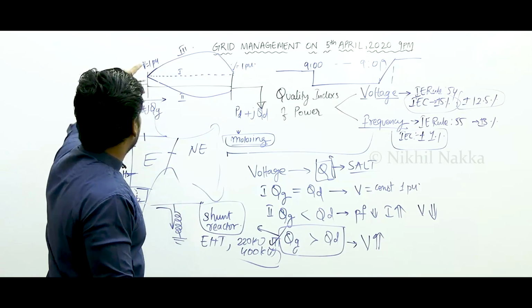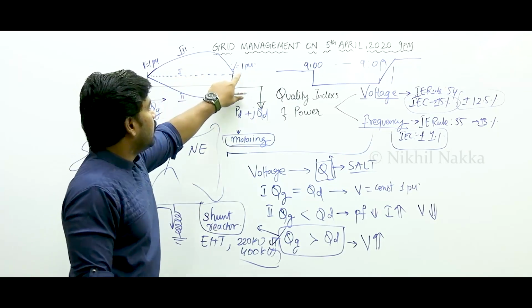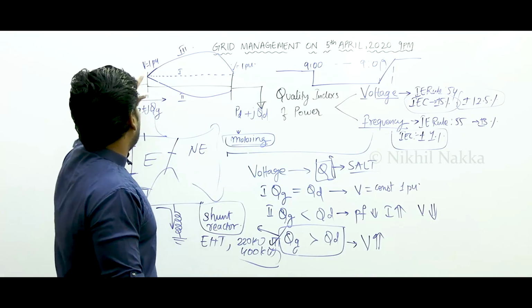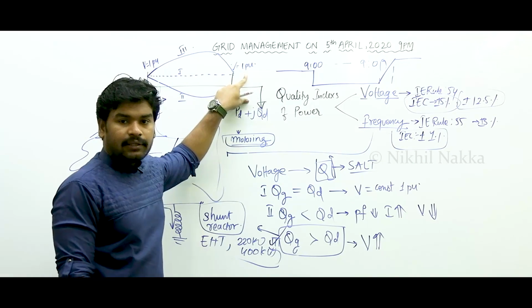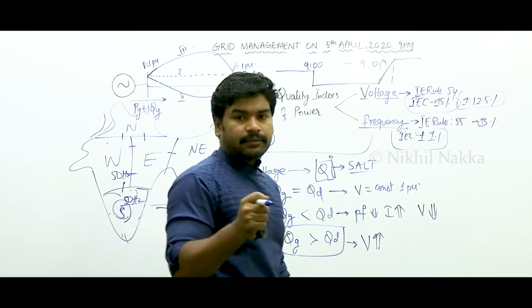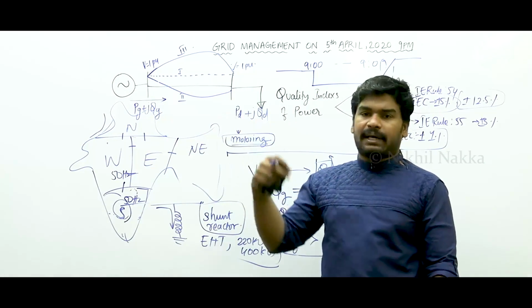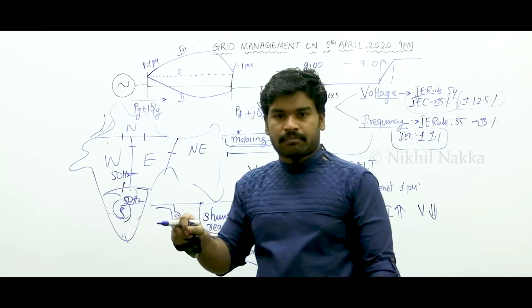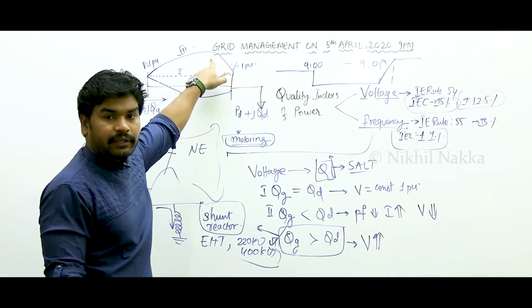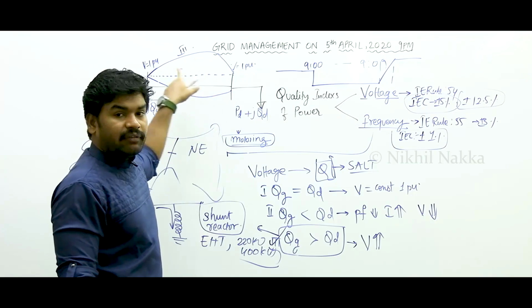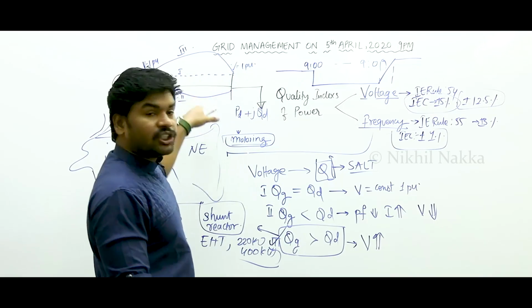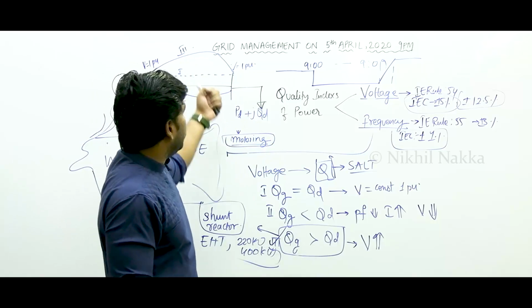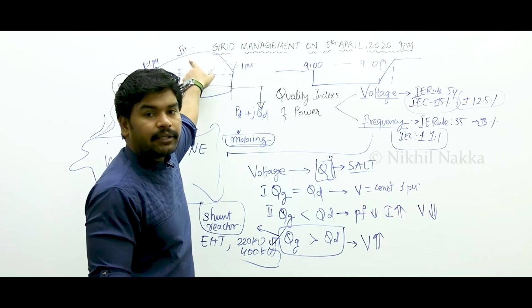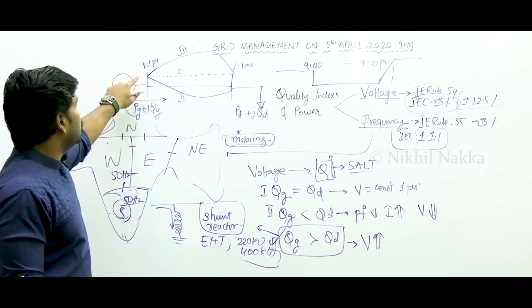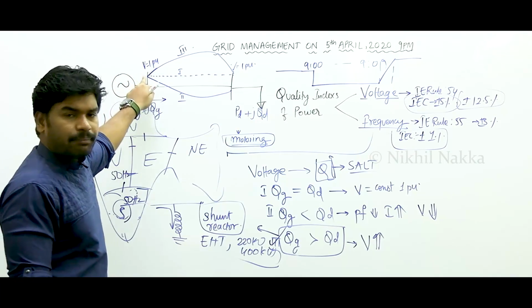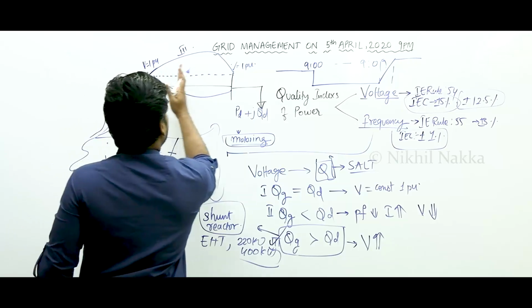What happens is, here you have transformers, and here too you have transformers. At the generating side and at the consumption side, maintaining voltage is a very strict parameter. So you maintain voltage, whatever the incoming voltage may be, by using tap-changing transformers. Of course, inside the line the voltage might be high, but at the end of the transmission line, in the transmission substations, you try to pull the voltage down to 1 per unit. Here you will simply supply at 1 per unit. But inside the transmission line, what is there?